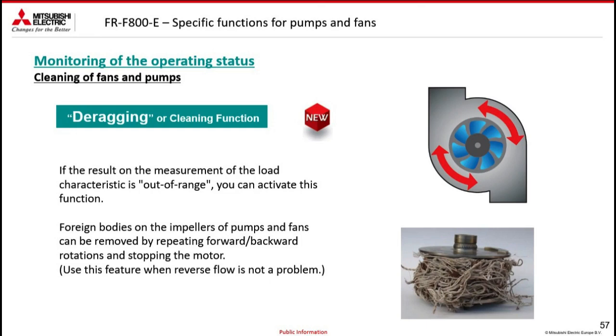As far as pumps are concerned, there is this very interesting function, namely deragging. Just think of a pump in which there is not only a liquid, but also foreign bodies in the duct. These bodies could block the pump impeller, thus causing problems when starting, as it could try to start but, failing to do so, could give an overcurrent alarm. This deragging function allows you to define how many times and at what frequencies to push back and forth to unblock the impeller and start everything more easily.